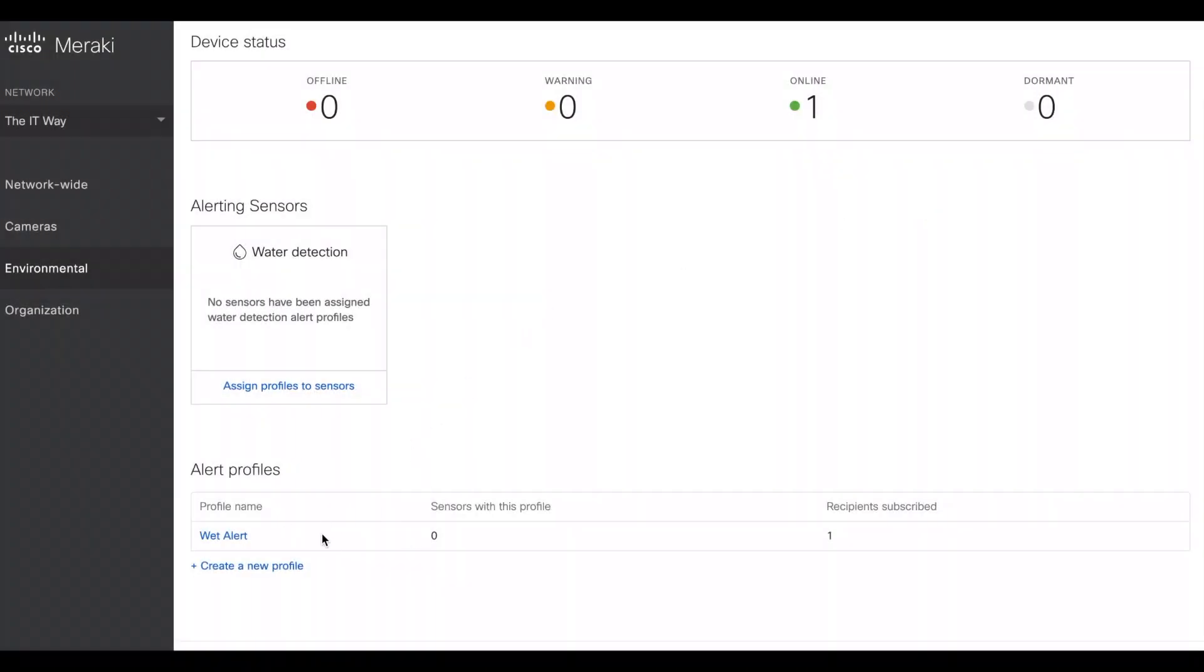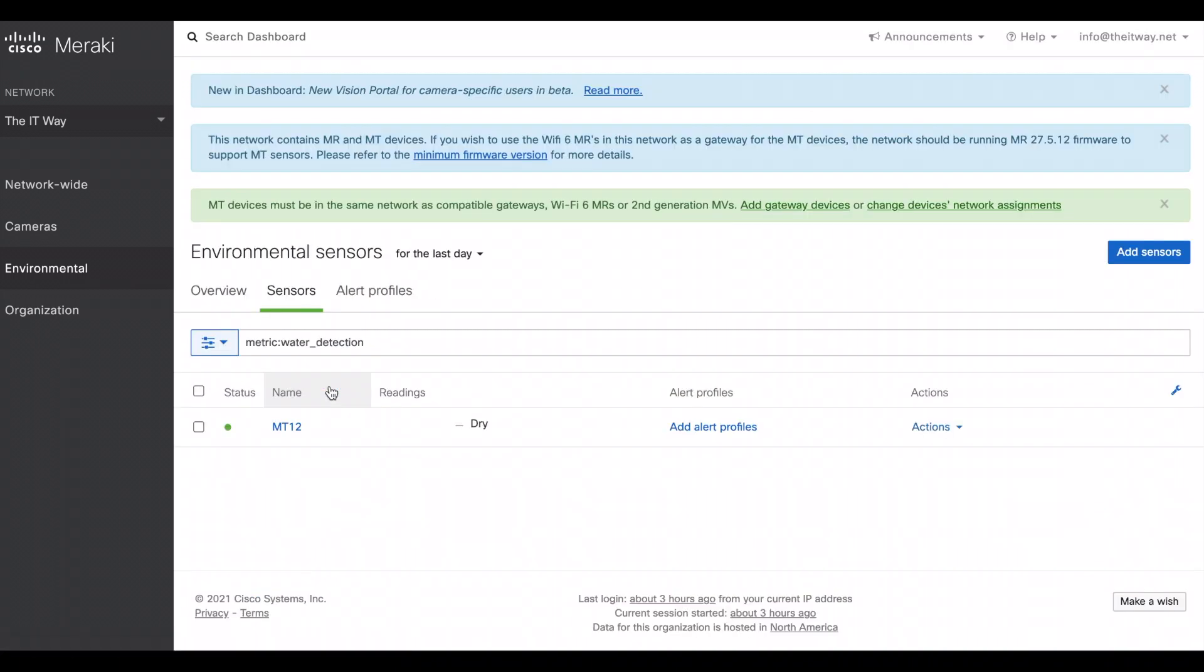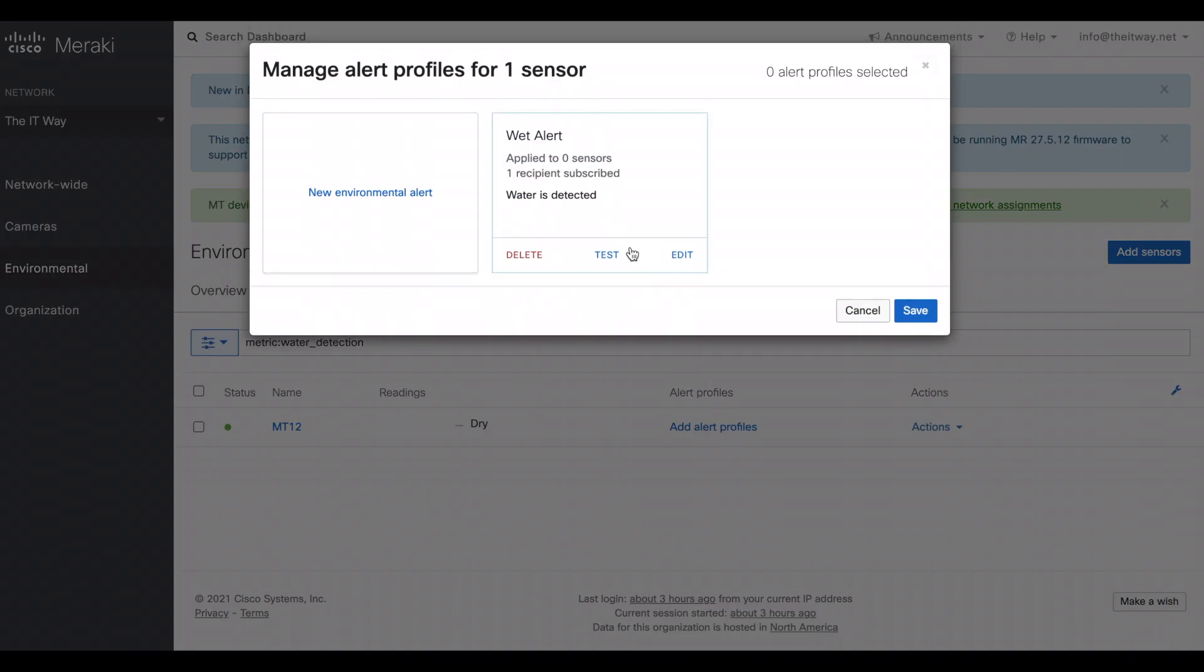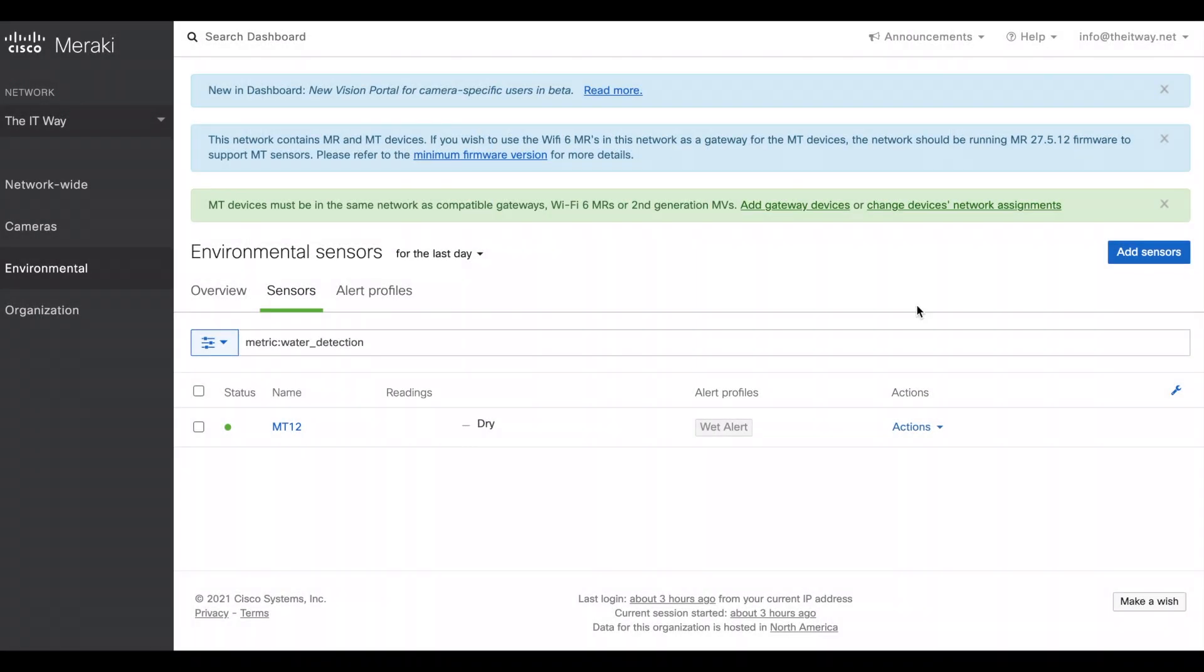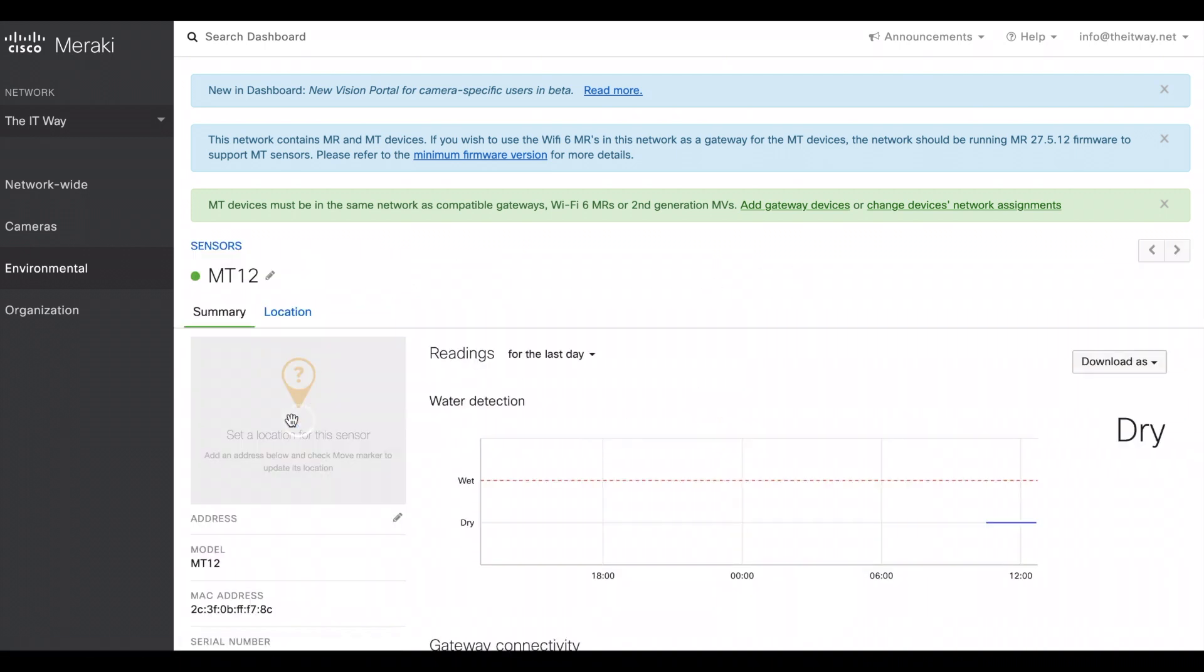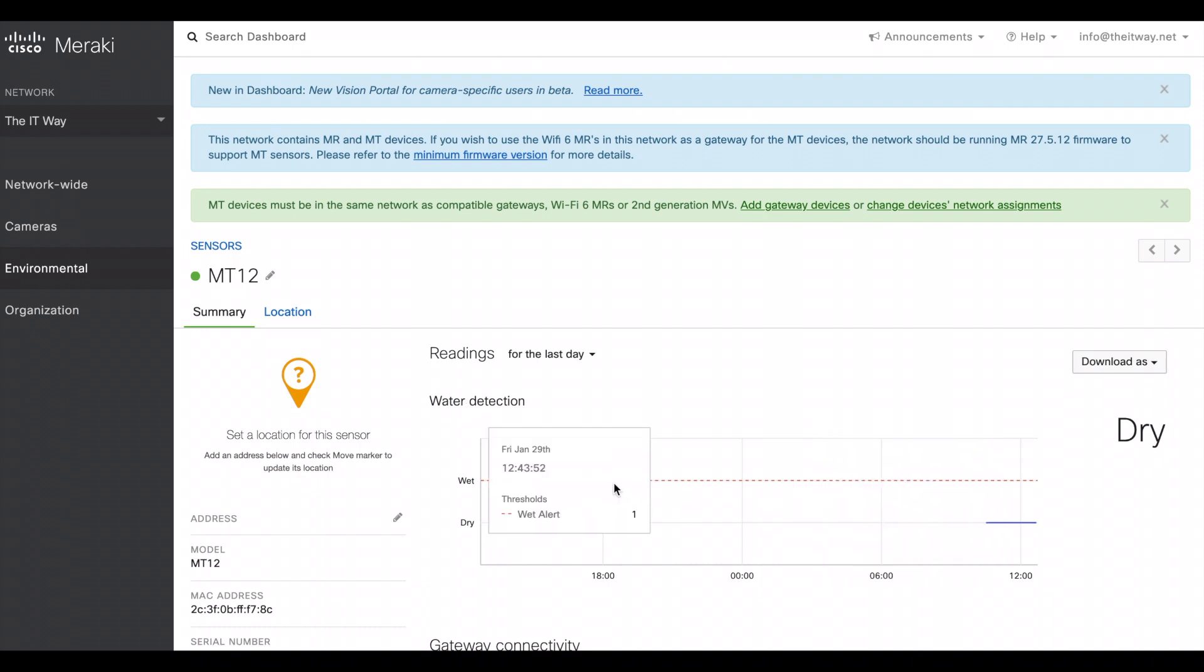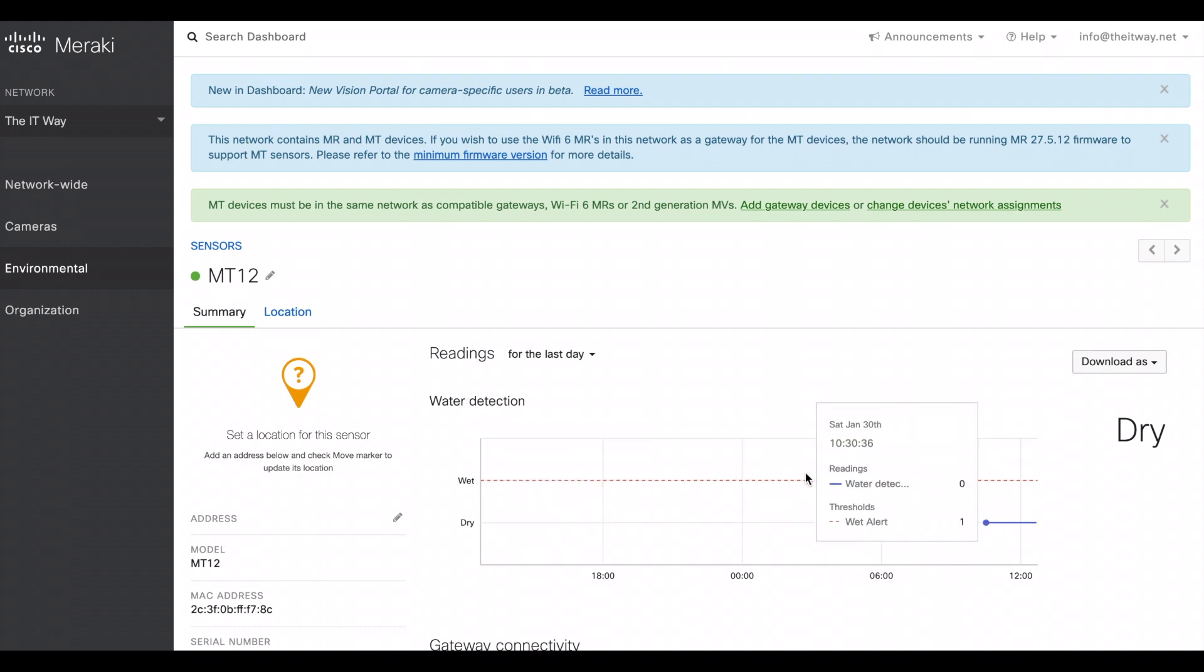After the profile is created, we have to assign that profile to the sensor. You go to the sensor and add the alert profiles. So here you have all the profiles available, and this time it's just one. It's going to apply to one sensor and we have just one recipient subscribed. If you save it, it's already there. So you see the wet alert. So when this sensor changed from dry to wet, so you see that threshold line as well, it's going to send the alert and the notifications to the ones that we selected.